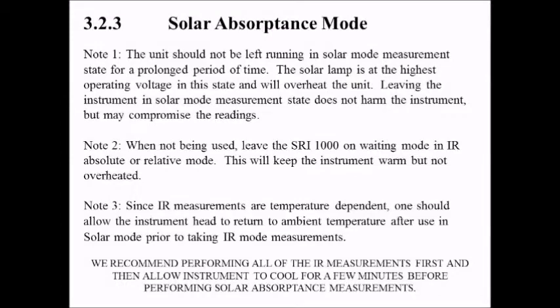Note 1. The unit should not be left running in solar mode measurement state for a prolonged period of time. The solar lamp is at the highest operating voltage in this state and will overheat the unit. Leaving the instrument in solar mode measurement state does not harm the instrument, but may compromise the readings. Note 2. When not being used, leave the SRI 1000 on waiting mode in IR, absolute, or relative mode. This will keep the instrument warm but not overheated.